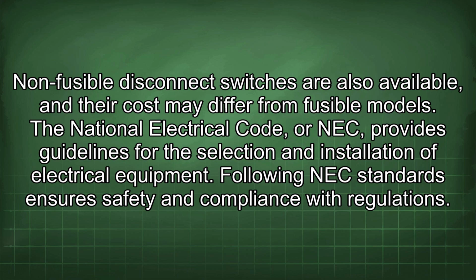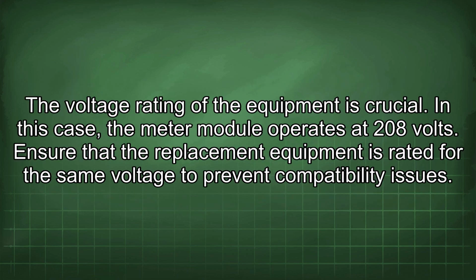The National Electrical Code, or NEC, provides guidelines for the selection and installation of electrical equipment. Following NEC standards ensures safety and compliance with regulations. The voltage rating of the equipment is crucial. In this case, the meter module operates at 208 volts. Ensure that the replacement equipment is rated for the same voltage to prevent compatibility issues.